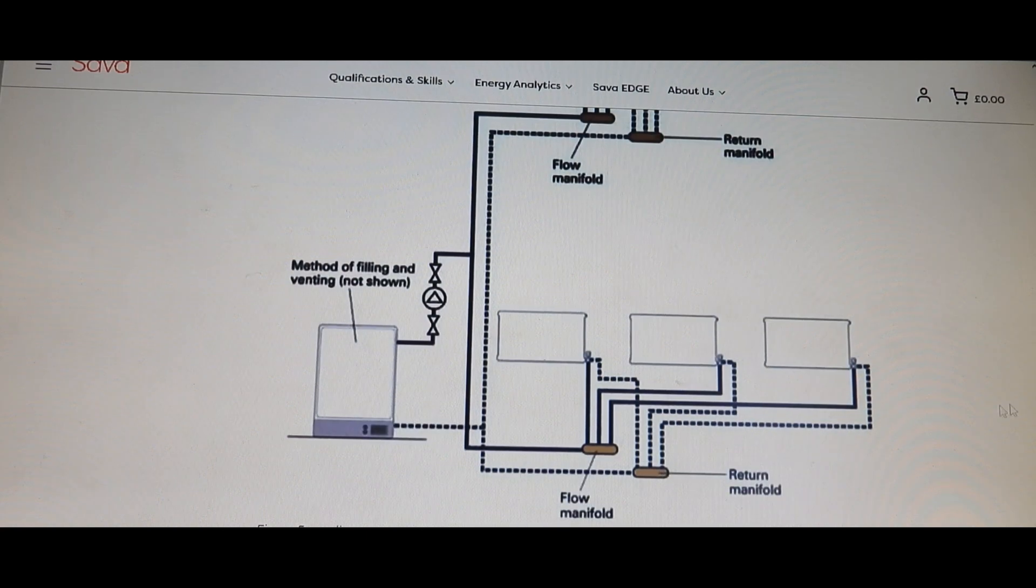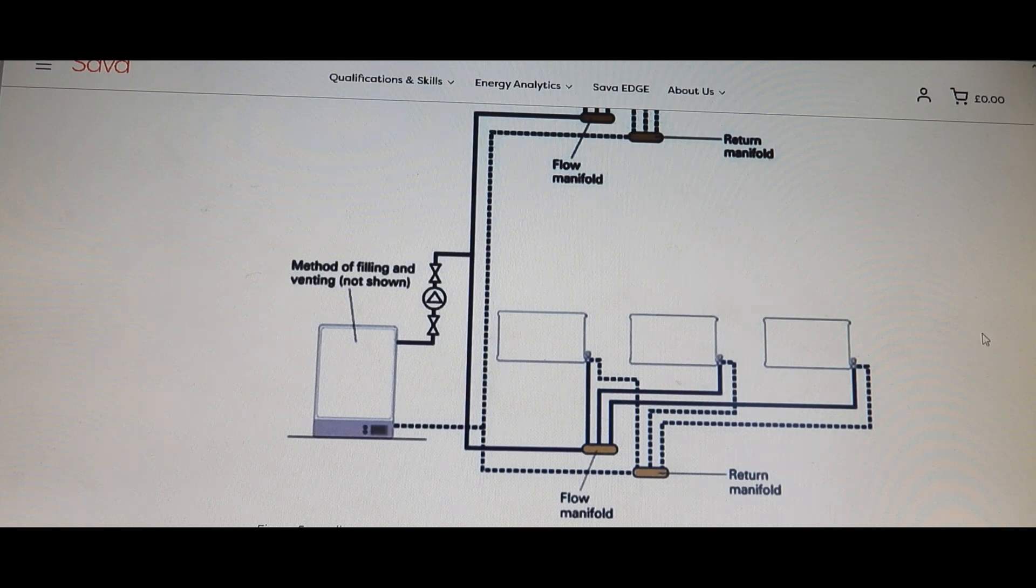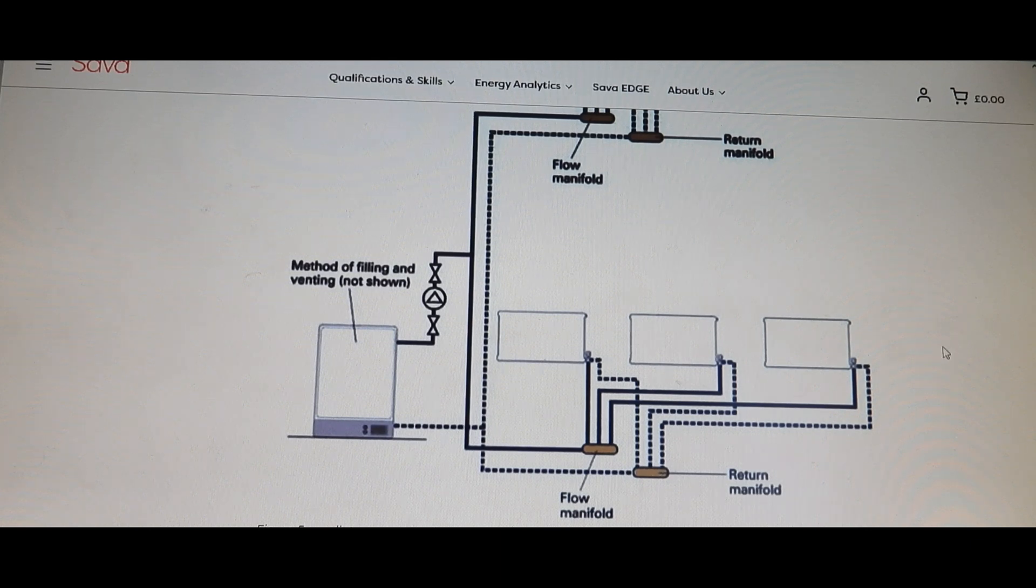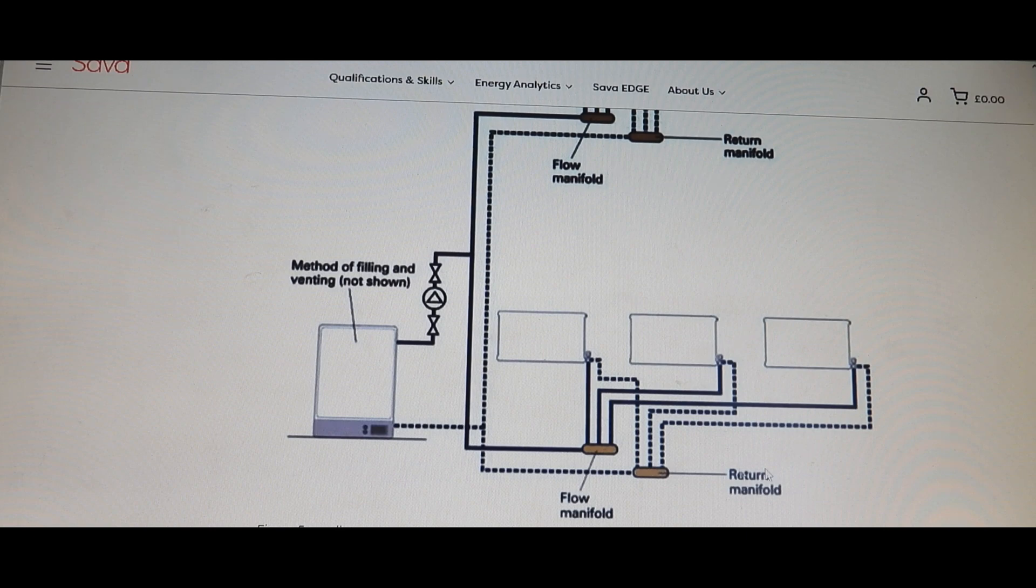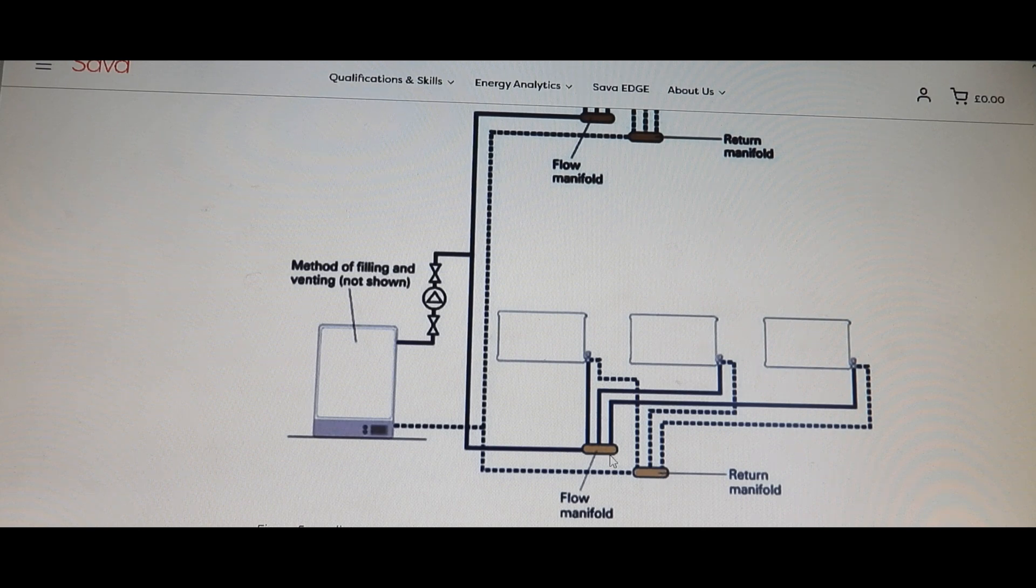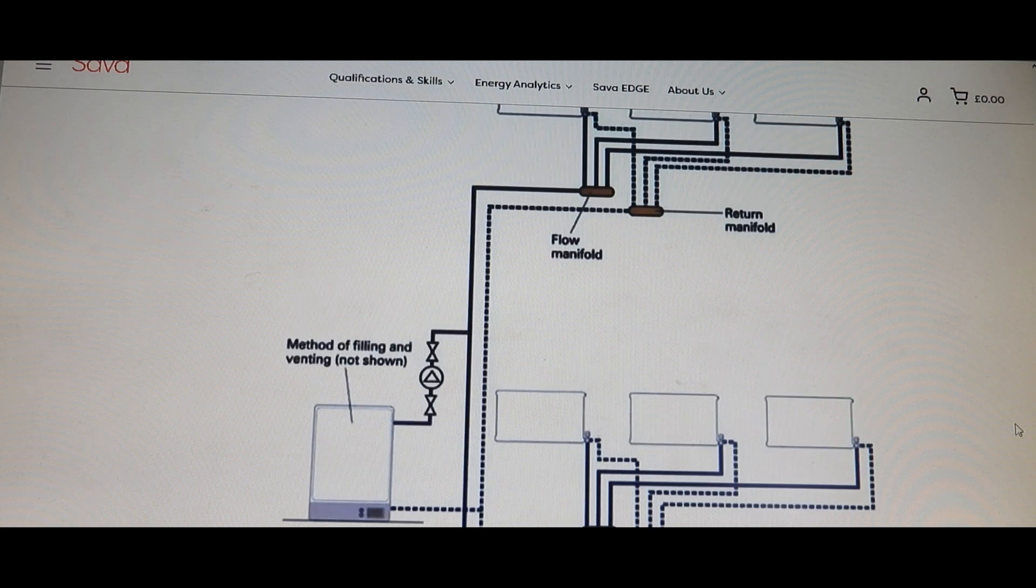Once you tee off a microbore pipe and run another rad around from it, the balancing act is quite hard to get right and can muck the whole system up. It's far better now to change the actual manifold itself so that you've got more ports. So you've got two manifolds here and have spare port access.